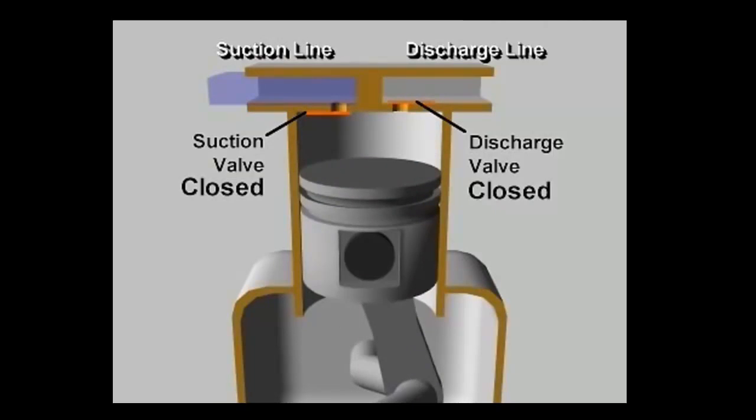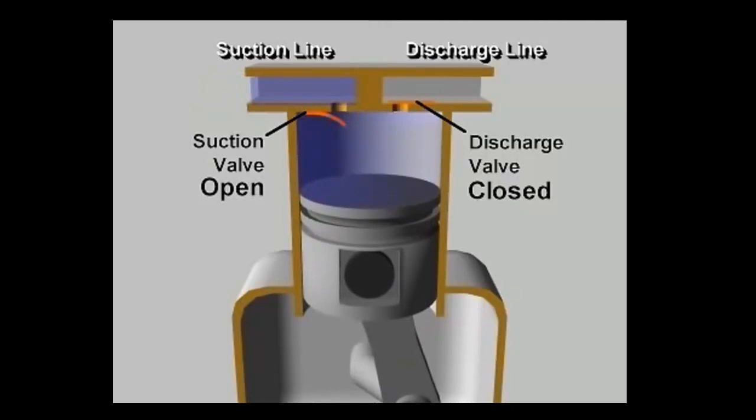Because both valves are closed, the downward moving piston reduces the pressure in the cylinder. As the pressure in the cylinder falls below the low side pressure in the suction line, the pressure difference opens the suction valve, letting refrigerant vapor flow into the cylinder.